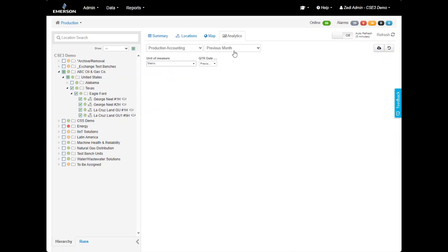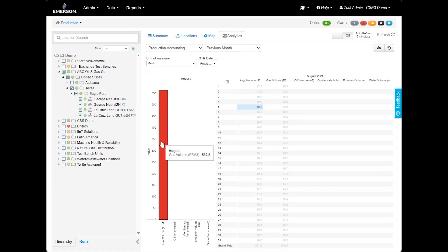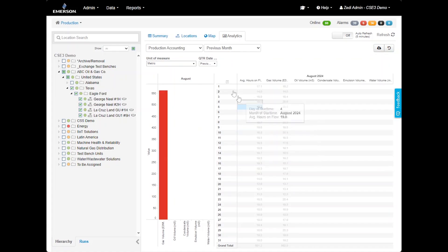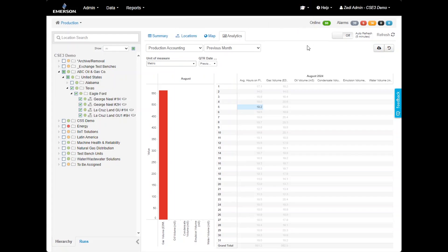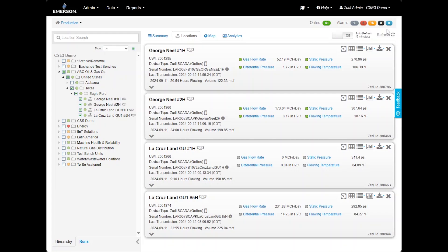Now let's discuss alarming. Each sensor on the site display can be configured to trigger alarms. These alarms can send notifications via text message, email, or both. Notifications can be directed to individuals or groups, allowing for prompt viewing and acknowledgement of alarms. In the top right corner of the home screen is the alarms dashboard. Here you will find different colored bubbles and numbers that represent current alarms across the company. The color codes are as follows. Gray is a no-communication alarm. Red is a high-high or low-low alarm. Orange is a high and low alarm. Black is a RTU alarm. And blue is missing flow parameter configuration.